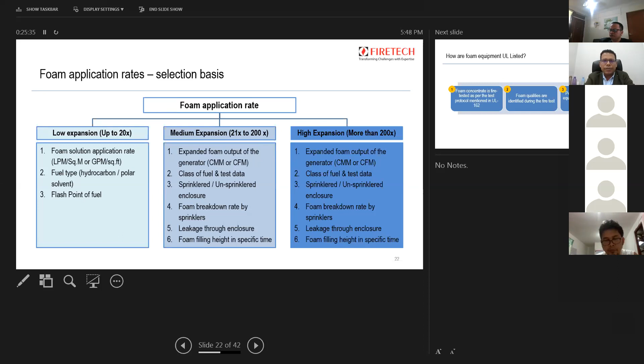Next, James. So the most important thing you have to understand is how the foam equipment you are listing is certified, what goes behind that. So first, a foam concentrate manufacturer formulates the foam. Either it can be AFFF or ARAFFF. These are different types of foam. So UL 162 is a specification which determines whether the foam and the equipment used with the foam is capable of extinguishing the fire or not. So only those equipments which comply with the requirements of UL 162 are certified.